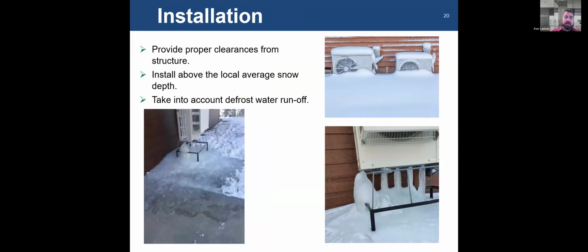Take into account the defrost water runoff. So what do I mean by that? We talked in earlier sessions about these units needing to go into defrost. Frost will build up on these coils in heating mode in the winter. They go into a defrost cycle. It defrosts all that frost that's built up on the exterior unit and melts it, and it drains out the bottom. These are a couple of photos from a heat pump in Minnesota. You can see how much defrost water, it's not even condensate, has been dripping out of this unit day after day, and it builds up. All right. And make sure your height is enough that you limit a situation such as this.